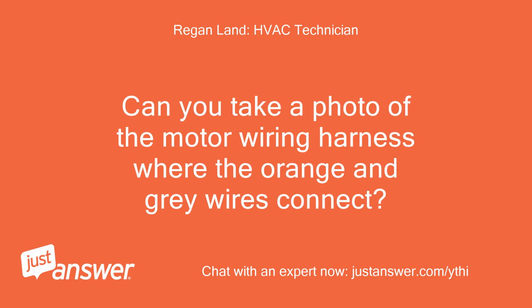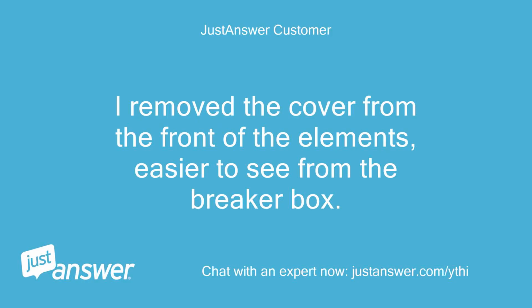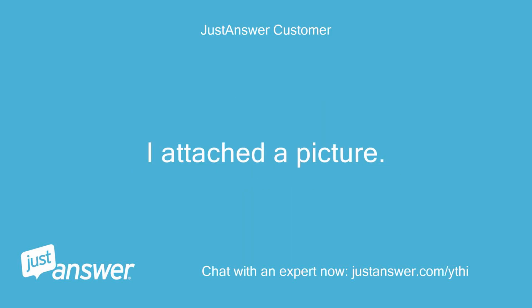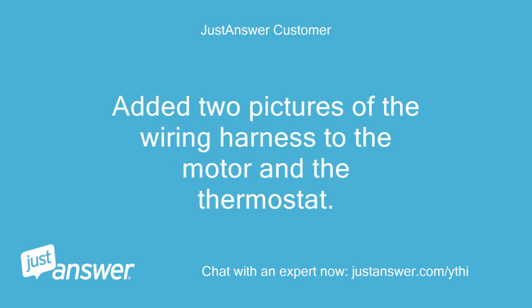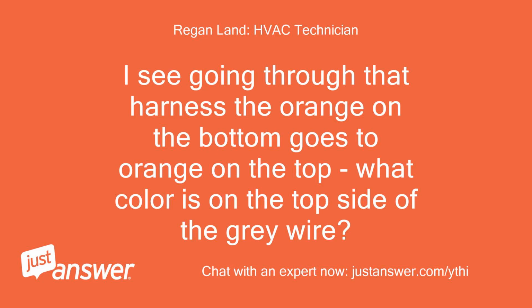Can you take a photo of the motor wiring harness where the orange and gray wires connect? I removed the cover from the front of the elements, easier to see from the breaker box. I attached a picture. Added 2 pictures of the wiring harness to the motor and the thermostat. I see going through that harness the orange on the bottom goes to orange on the top.